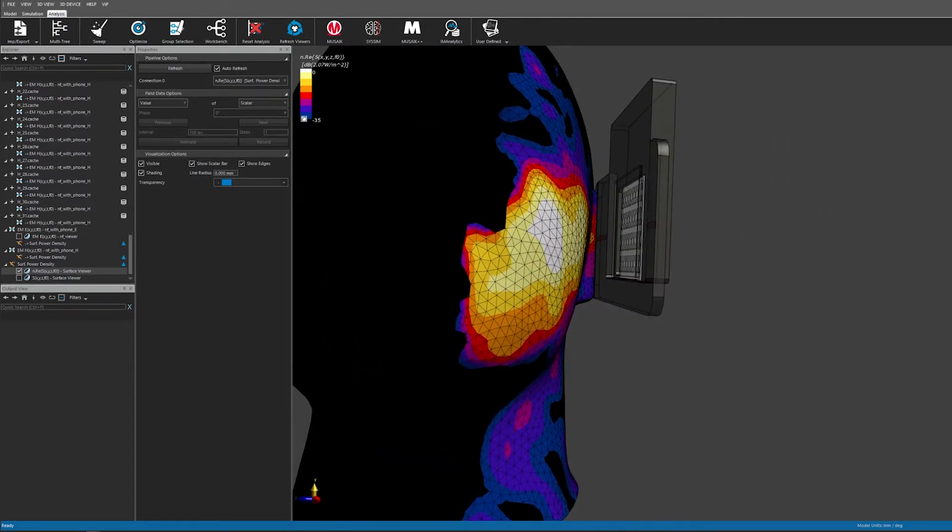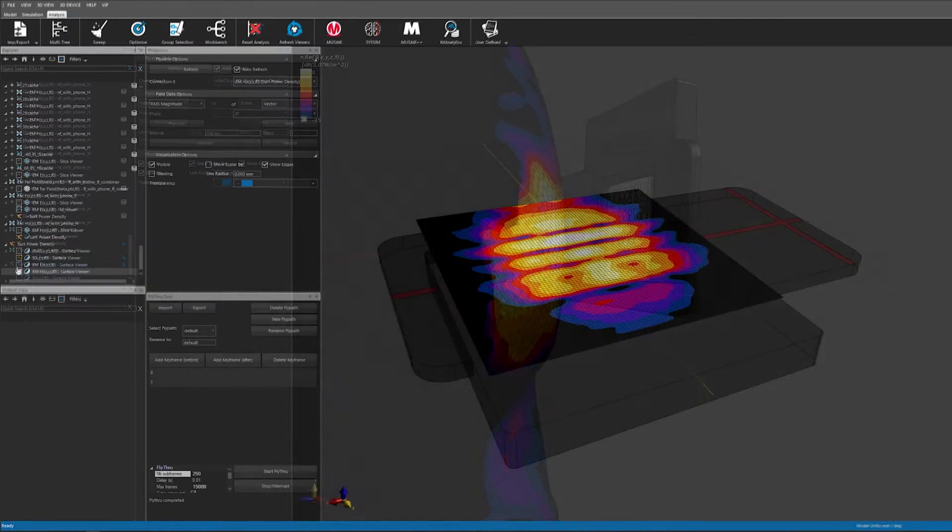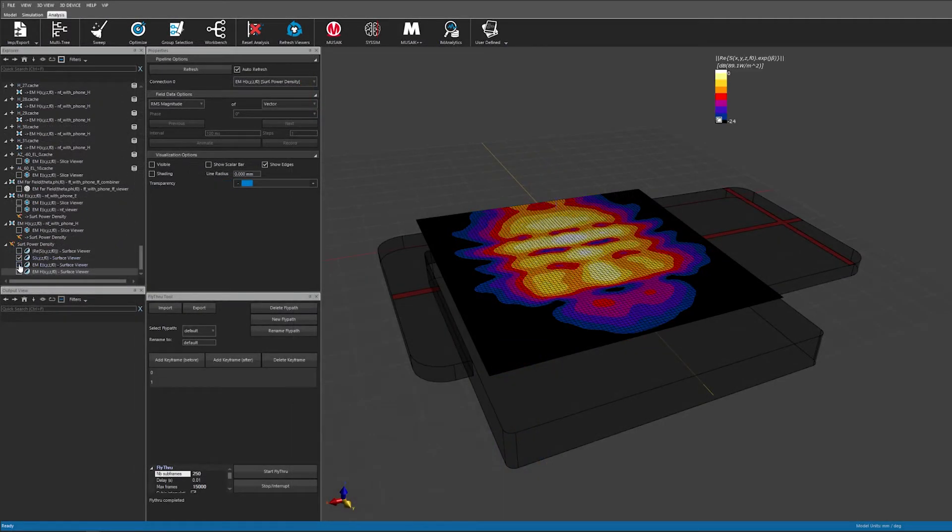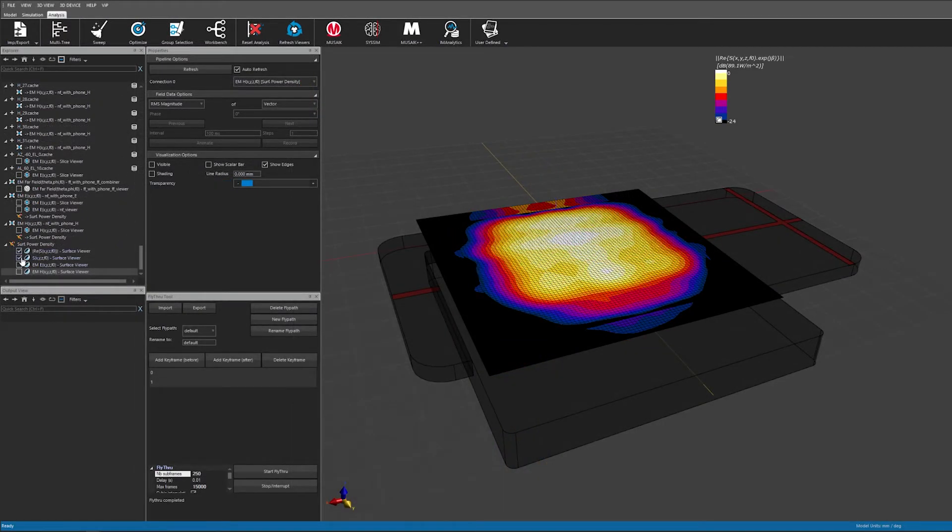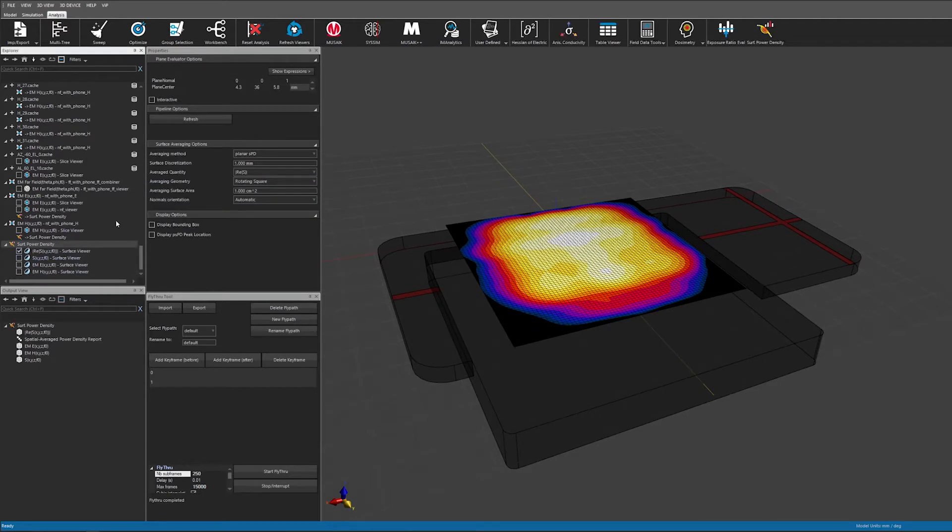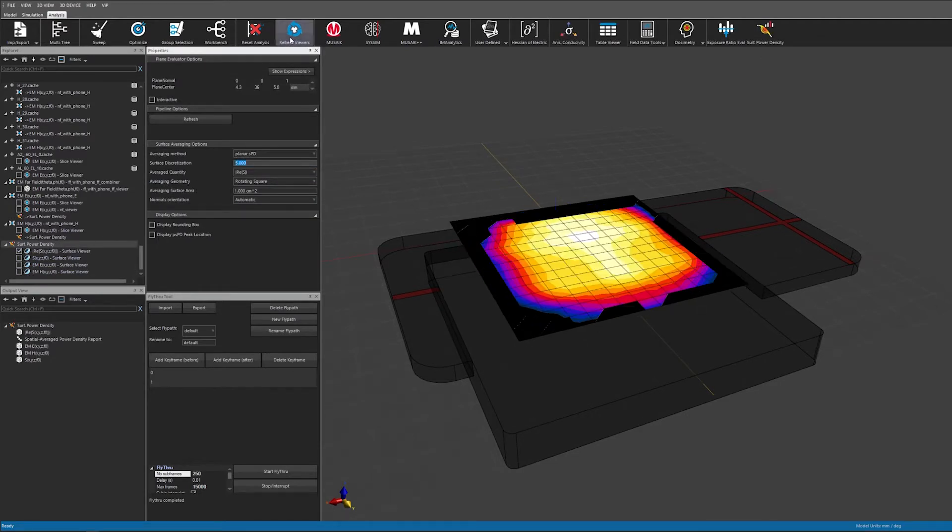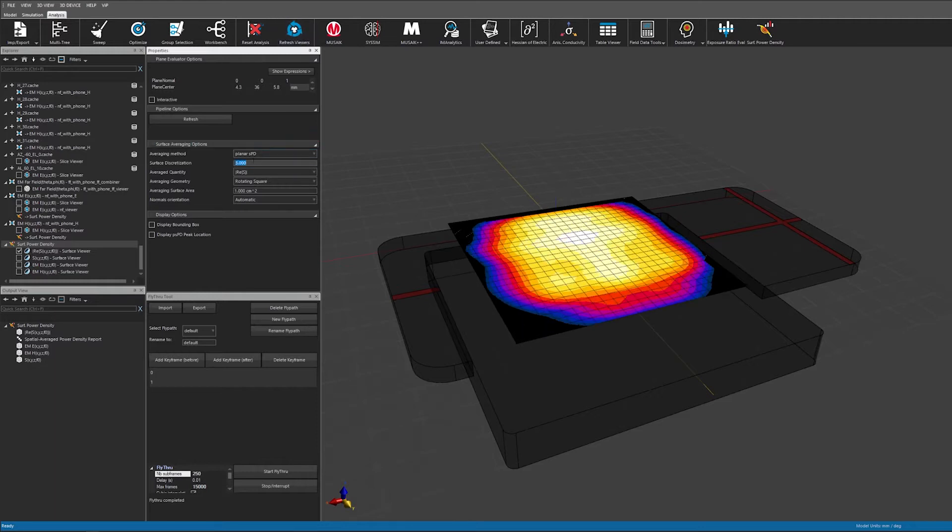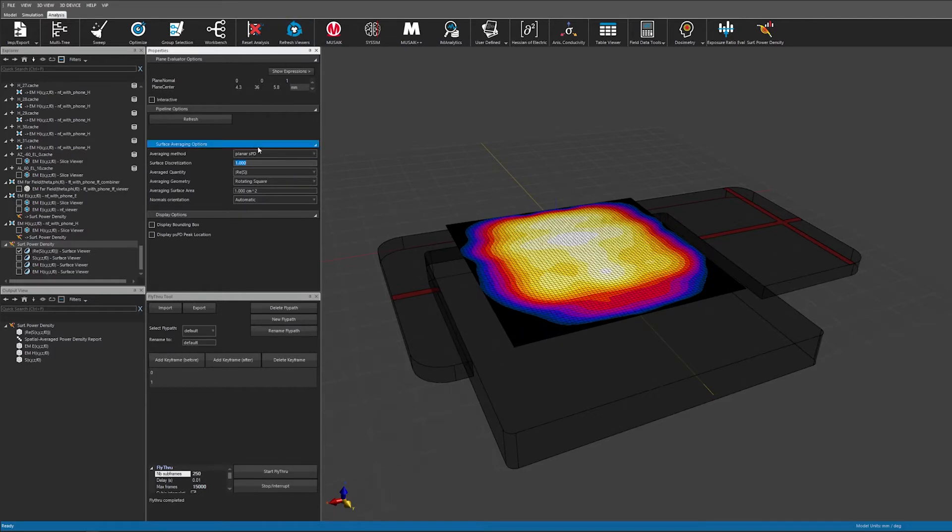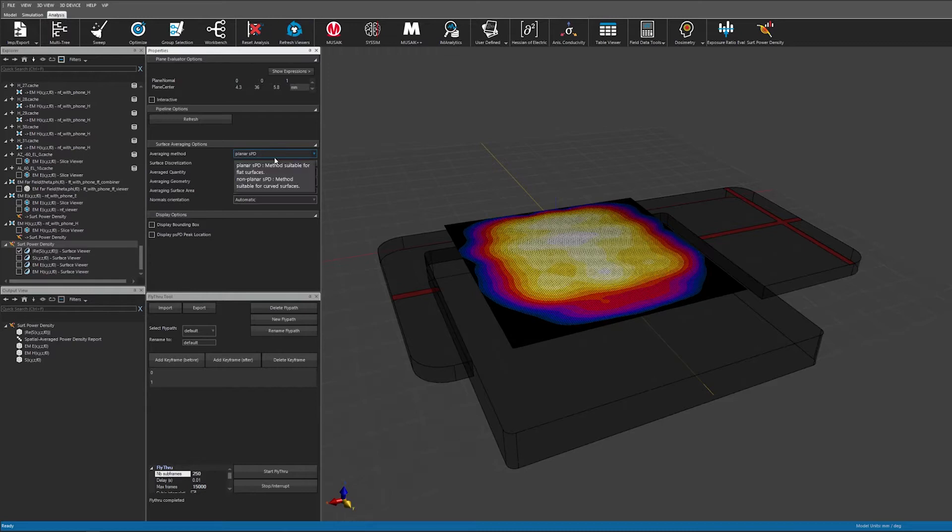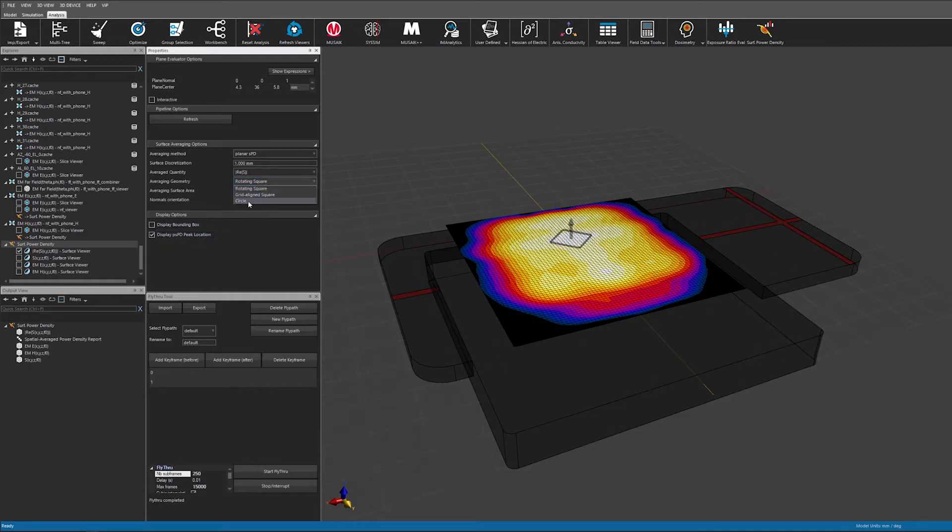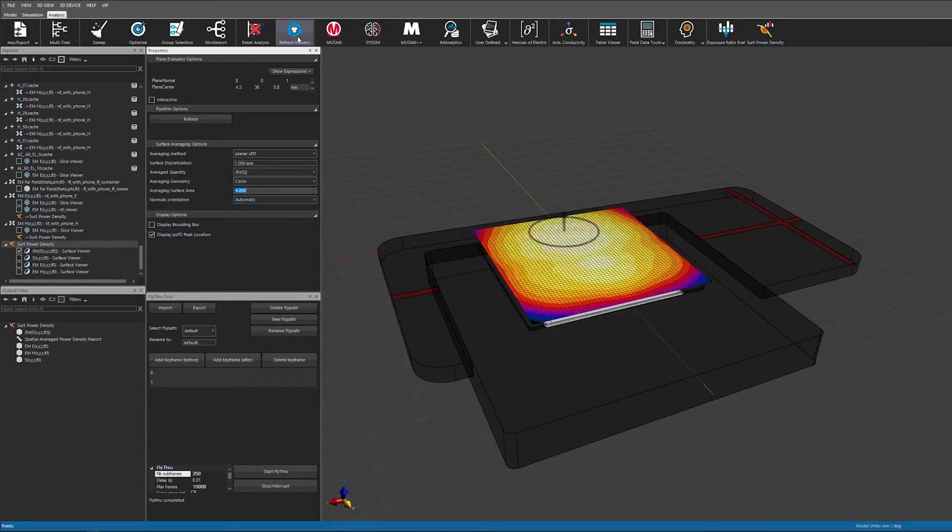The fields are first interpolated onto the discretized evaluation surface and then an averaging algorithm is applied. The evaluator lets me choose the refinement precision of the surface mesh. The standard requires a discretization of 1 mm or less but I can use larger values for ultra-fast first approximations.